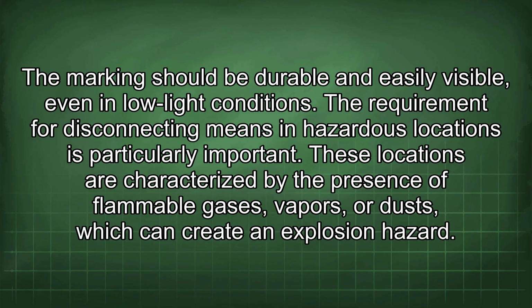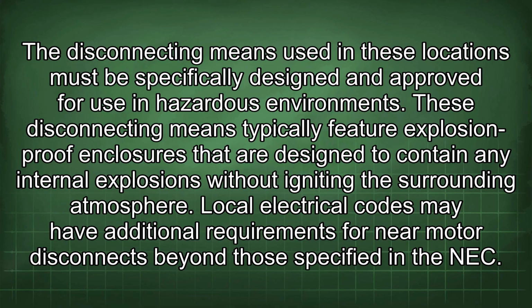The requirement for disconnecting means in hazardous locations is particularly important. These locations are characterized by the presence of flammable gases, vapors, or dusts which can create an explosion hazard. The disconnecting means used in these locations must be specifically designed and approved for use in hazardous environments. These disconnecting means typically feature explosion-proof enclosures that are designed to contain any internal explosions without igniting the surrounding atmosphere.